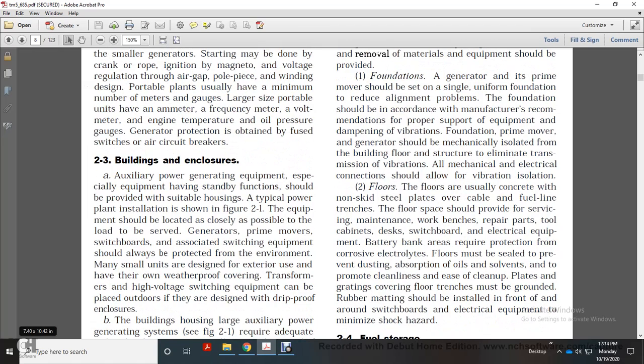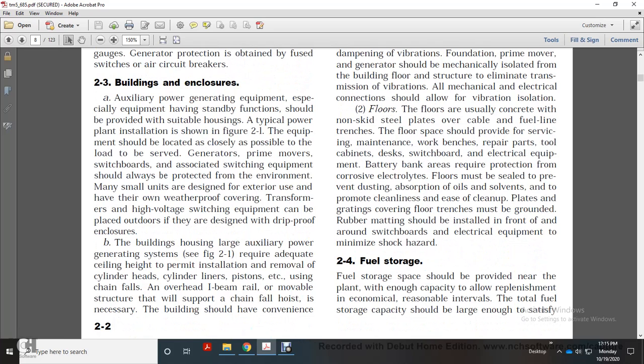Generator protection is obtained by fuse switches and air circuit breakers. Building and enclosures: An auxiliary power generator designated as standby should be provided with suitable housing, as shown in Figure 2-1. The equipment should be located as closely as possible to the load to be served. The generator, prime mover, switchboards, and associated switching equipment should always be protected within an enclosure. Small units may have their own weatherproof covering. High-voltage switching equipment can be placed outdoors under a drip-proof enclosure.